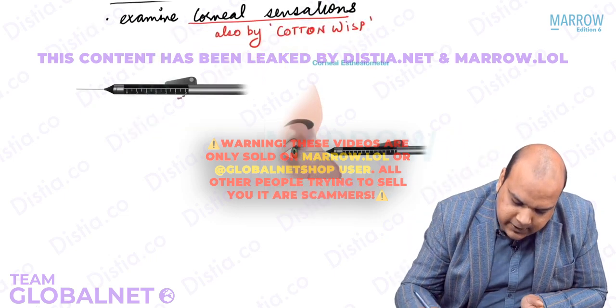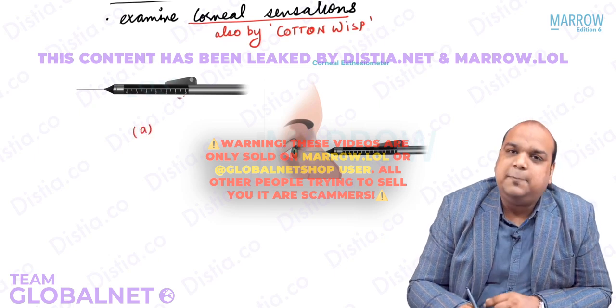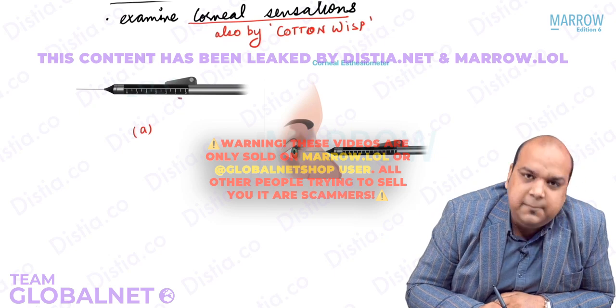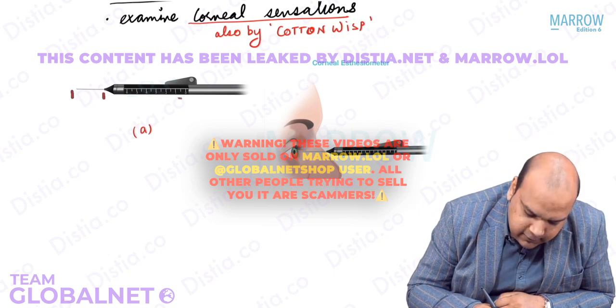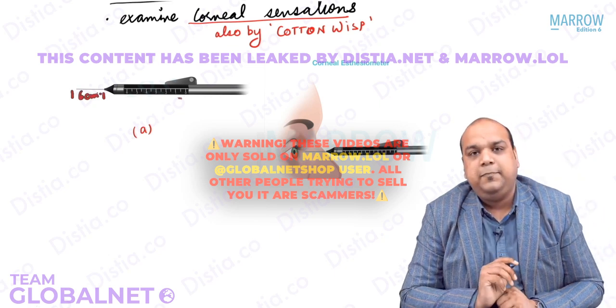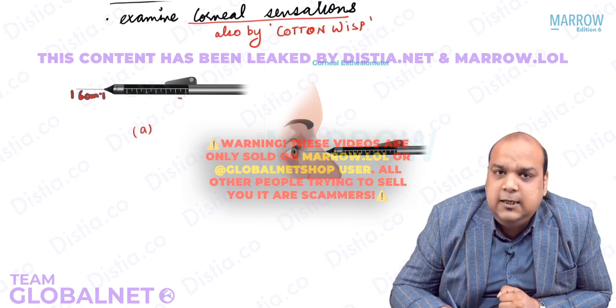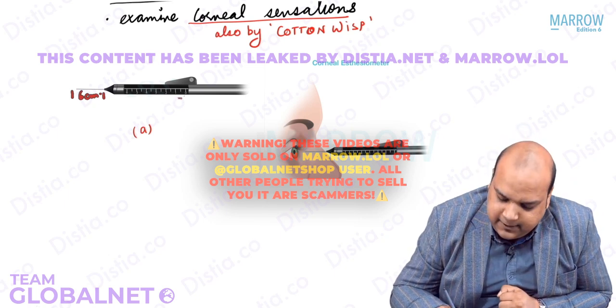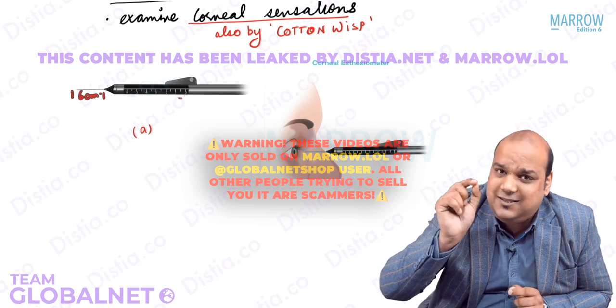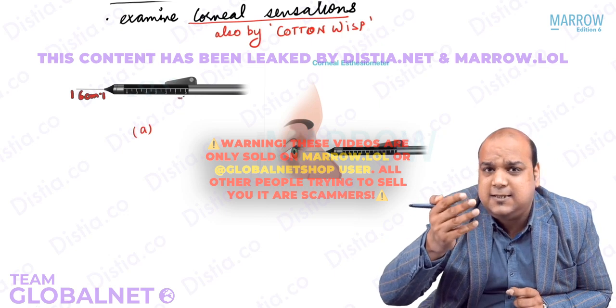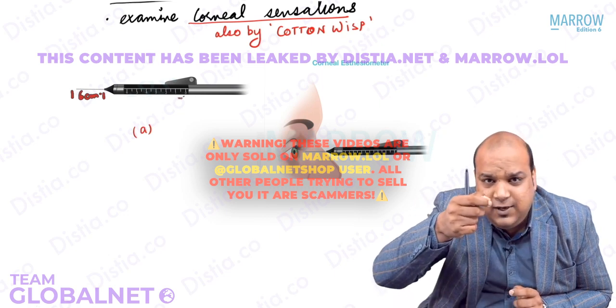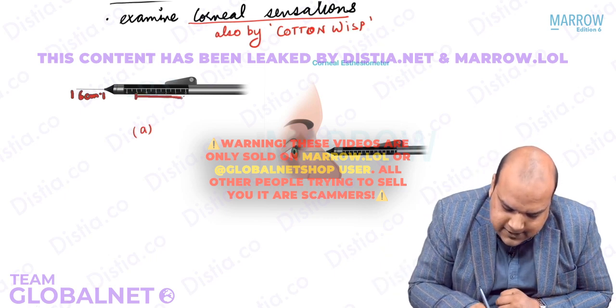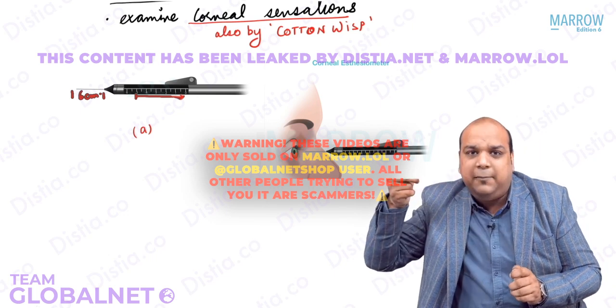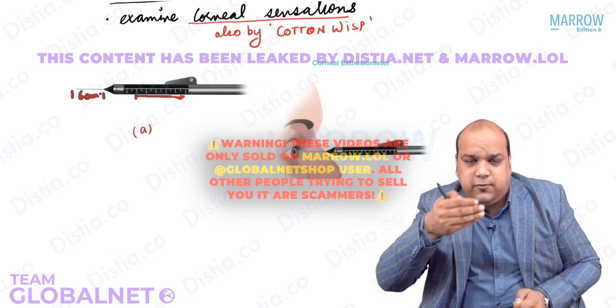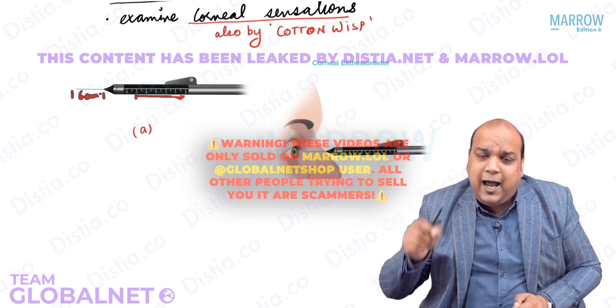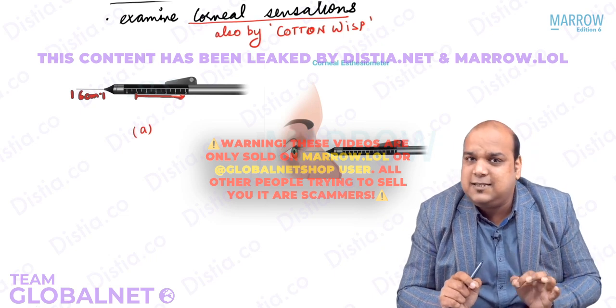Yes. So this instrument, everybody, this image that you see, image A here, is a pen-like instrument with a thin filament which comes out from this. The maximum length of this thin filament is 6 centimeters. The filament will touch the cornea of the patient. We open it completely first to 6 centimeters. We touch the cornea. We see whether the patient is able to feel the sensations or not. If the patient is not able to feel the sensations, we retract. I hope you are able to see this scale here, everybody. So we are able to retract this filament. We retract it by 0.5 centimeter, from 6 to 5.5, 5, 4.5, 4. At whichever point the patient is able to feel the sensations, we record that.